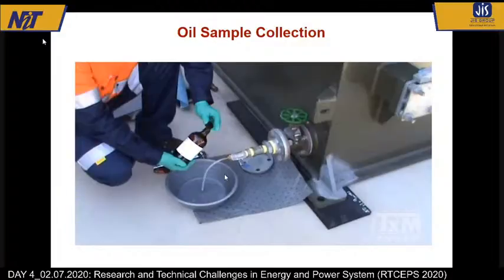The photograph I am showing is of what is called an oil drain valve. All our young participants, I think you should always see a real-life transformer. These oil drain valves are mandatory for transformers. Generally, this green color valve, you can see, will be closed so that oil will not come out. But for any reason, if we want some oil sample to be taken, it is very simple. We will open this valve and, just like a tap, we will collect the oil and again we will close it. So we don't have to switch off the transformer also. The transformer can be running, but still we can collect the oil sample. This is extremely important from our monitoring point of view. So this is one insulation that we have.